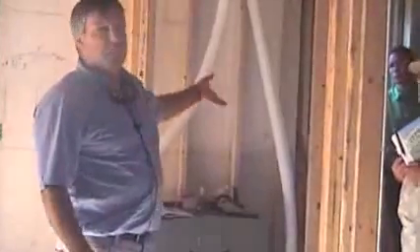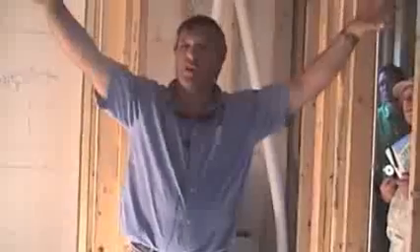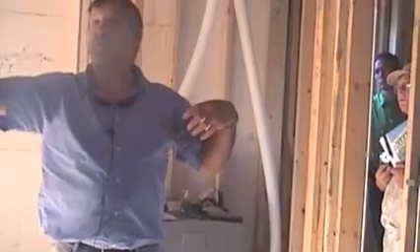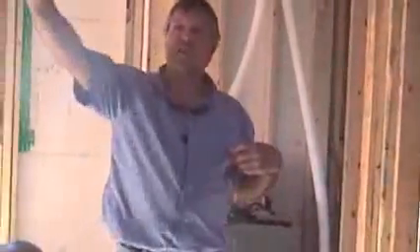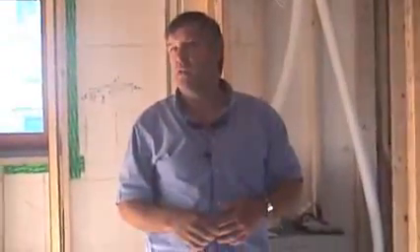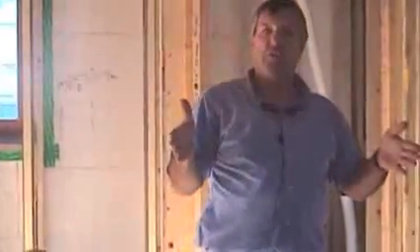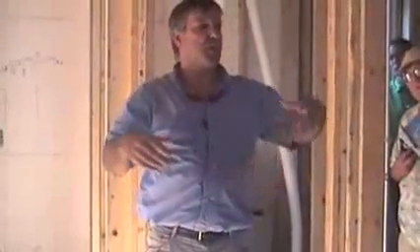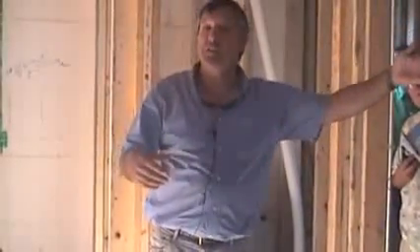If you look, most of the wet stuff, the bathrooms are all here, and here's the unit. So they're all short runs. And then the bedrooms are all out there and over there, and they're all long runs. So your total duct length is much higher on the supply side than it is on the return side, which means there's more static pressure, more resistance in longer tubing, and also 90-degree bends are a very important factor. So when we add it up, when we run both fan motors at 50%, you'll have maybe 135 CFM on your return side, but the supply side with the longer runs was only running 120 CFM.